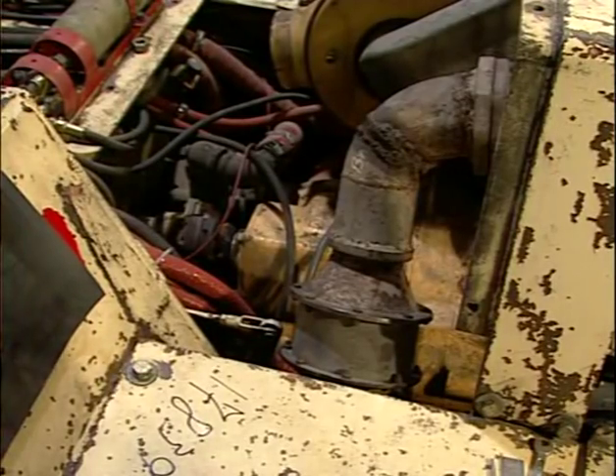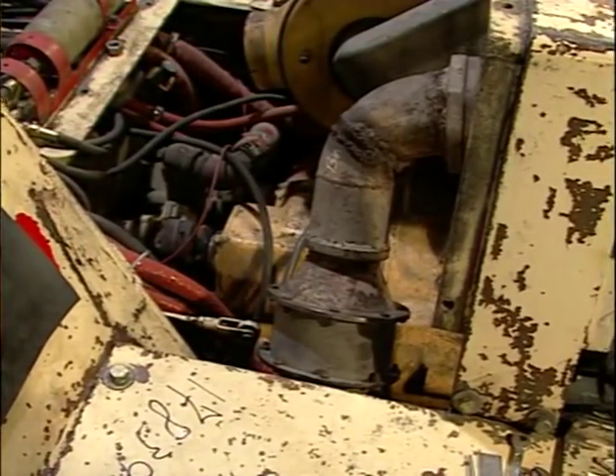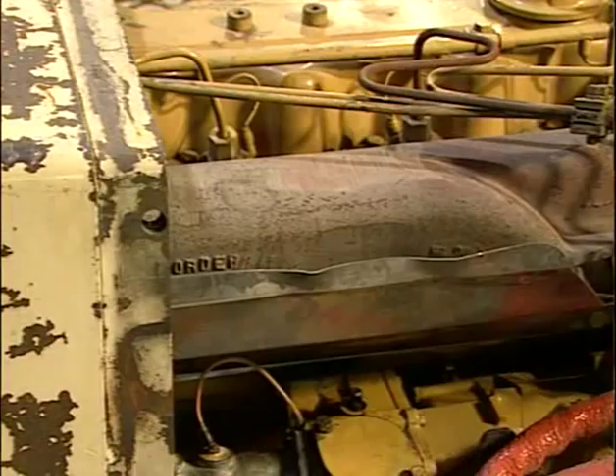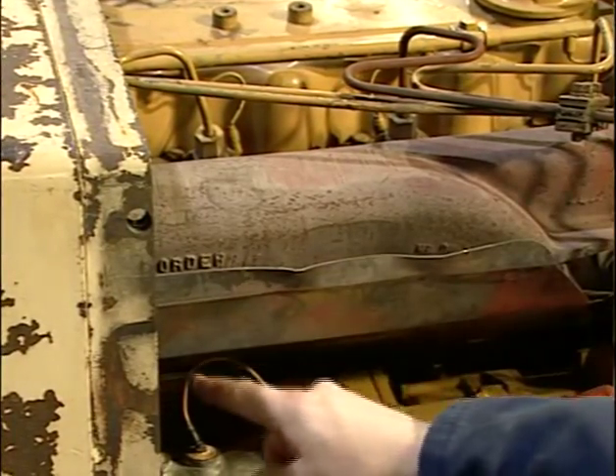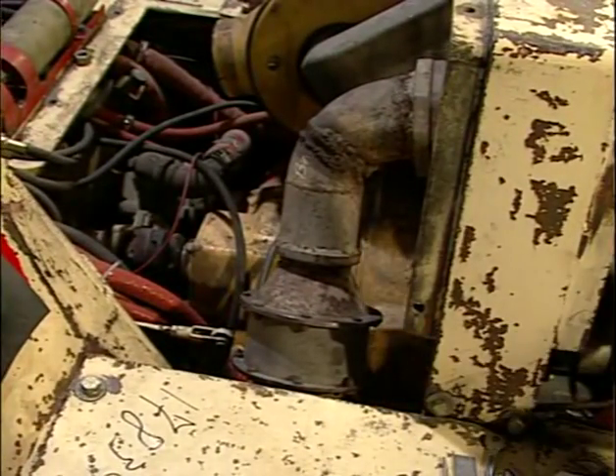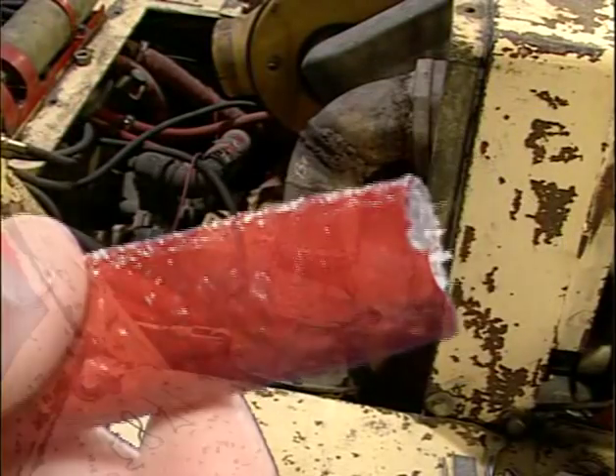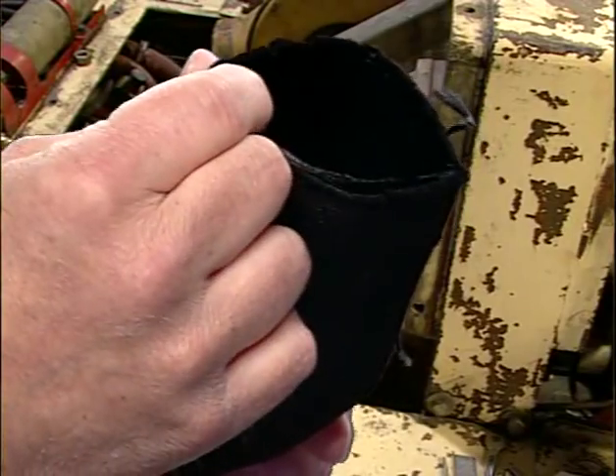The regulation is meant to prevent the spray from ruptured hydraulic and lubricating oil lines from being ignited by contact with engine exhaust system component surfaces such as the exhaust manifold and the exhaust pipe. Due to the inadequate size of this deflection shield, diesel fuel could come in contact with the hot exhaust manifold or exhaust pipe. Additional protection such as ceramic coating or a jacket on the exhaust manifold and exhaust pipe, or flame resistant sleeves or conduit on the hydraulic hoses, should be used.